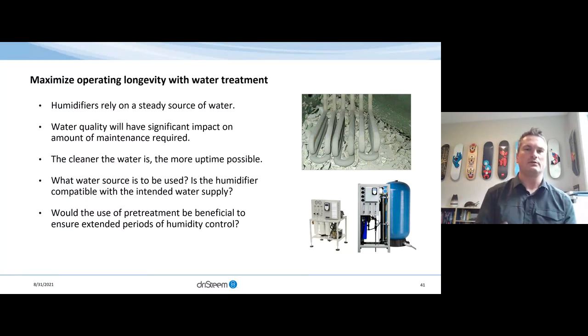And when you're spraying it or fogging it, it creates dusting. And this dusting can lead to a lot of other havoc later on. So pre-treatment's really important in the approach on adiabatic. If we're looking at media, it can create fouling and scale buildup, increasing the pressure drop of the system and leading to challenges related with that.